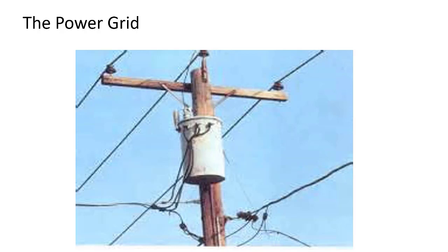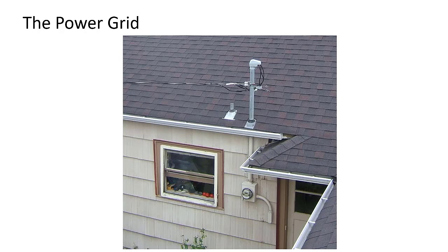Can transformers are quite common in the city and are usually mounted on utility poles. They can be mounted on the ground, oftentimes in the suburbs. The power from the substation coming into this transformer is 7,200 volts. The electricity is then split off to 4 or 5 different homes or businesses. In most cases, the electricity going into a home is 200 amps at 240 volts.